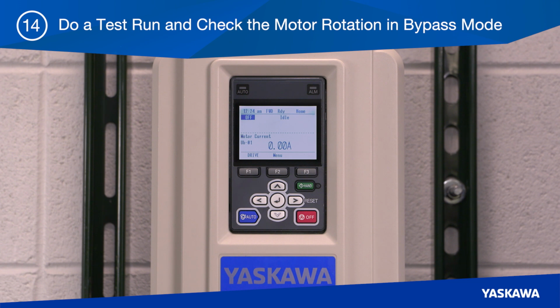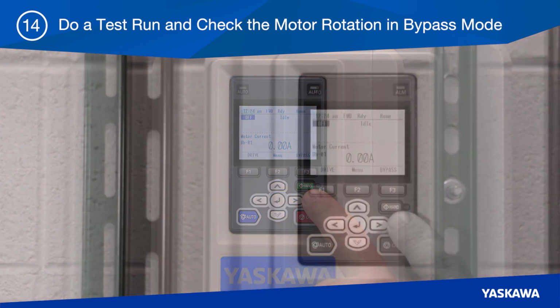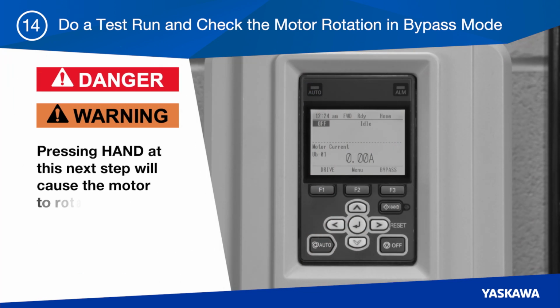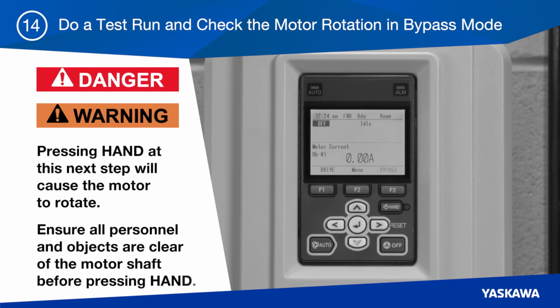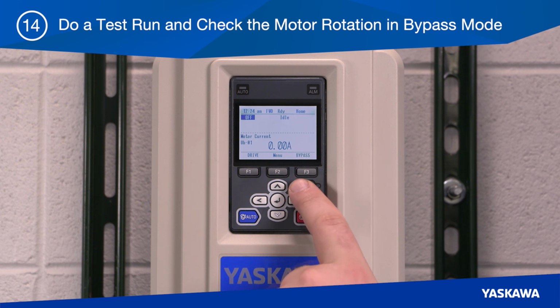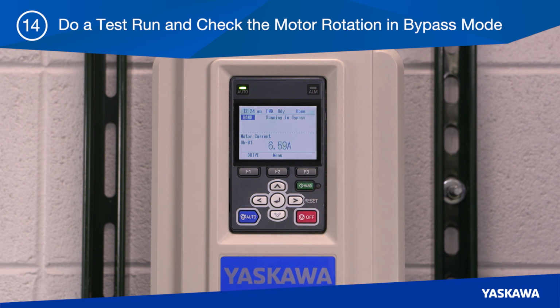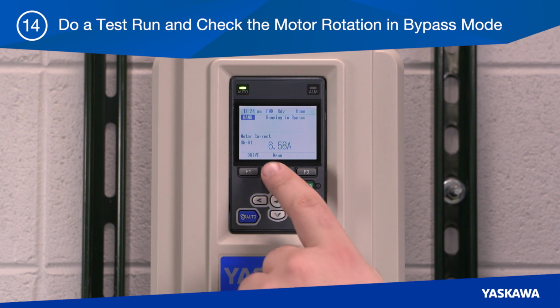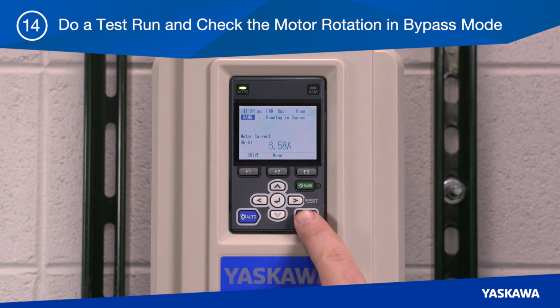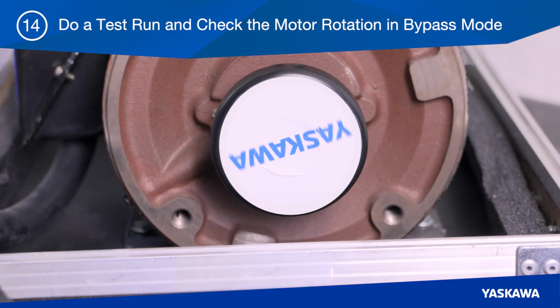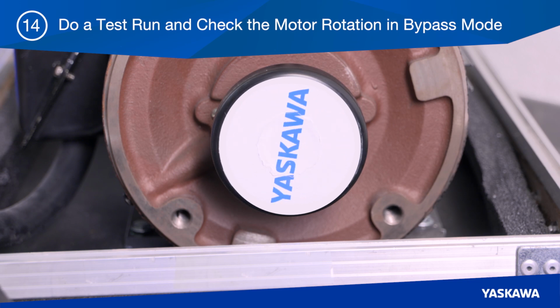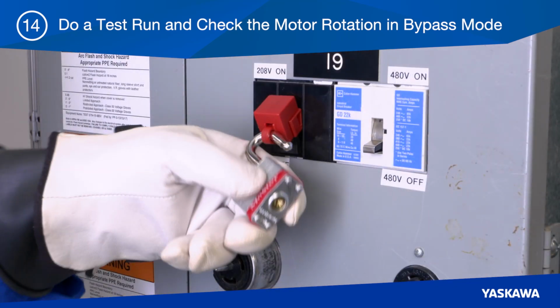Now, ensure proper safety precautions are taken before pressing the hand button. Warning: the motor will run at full speed. Check dampers and/or equivalent devices to avoid mechanical damage. Press the green hand button and again review amps in bypass mode U1-01 for your application. Shut down the system and observe the motor rotation direction. If motor rotation is incorrect, perform all the required lockout-tagout procedures.